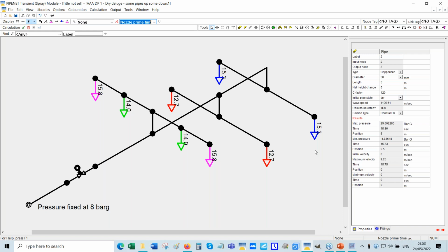an engineering company which had great difficulty in reducing the discharge time of a deluge system. And what the problem was, it was a problem that was extremely difficult to solve, because this pipe here had an elevation of around 35 meters or 40 meters.